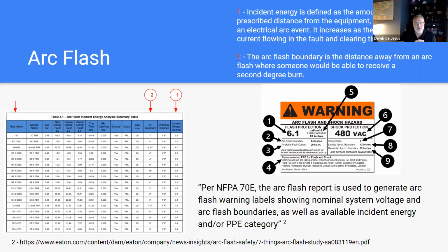Vendors provide things called chicken switches, or an HMI panel where the owner can activate a breaker to maintain distance from that piece of equipment. So there are pieces of equipment that come with accessories to help owners maintain distance without investing in large, rarely used PPE. That's something you could look for during your design review—are those accessories available to the owner?